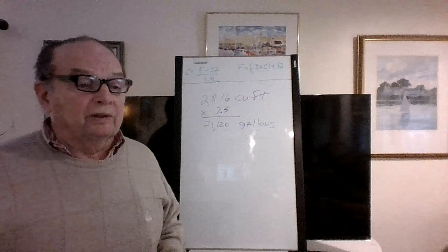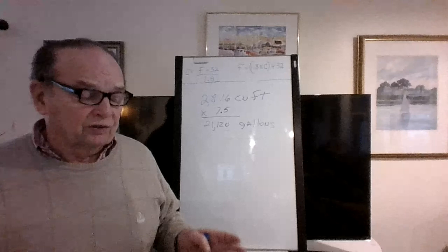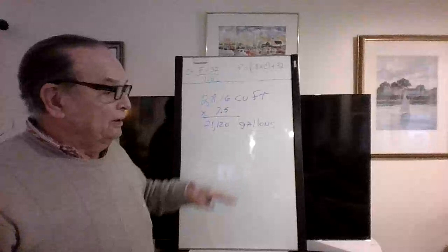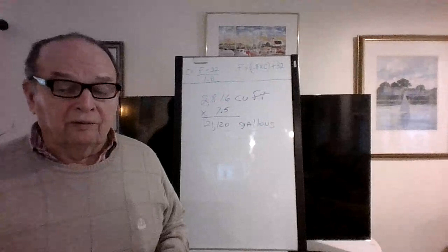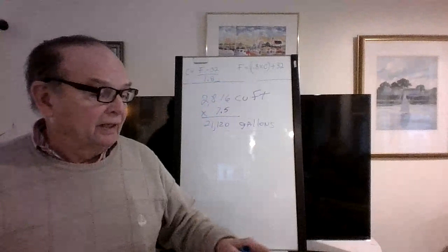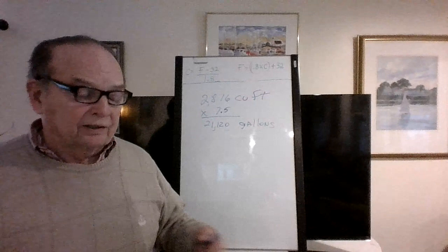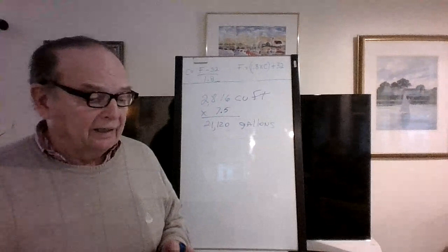Now the water never got hot enough. I don't know how it was insulated. I suspect they had insulation all around the concrete. I didn't see that going. But the water was not hot enough to run baseboard. By the way, you should know that baseboard cannot run less than 160 degrees. Under that, it's not at all effective. Even 160 is not the best. It's rated at 185. That's where you get your 600 BTUs per foot. That's where they size it up. That's how your heat estimators decide what you got. It's at 185. That's how they size it.